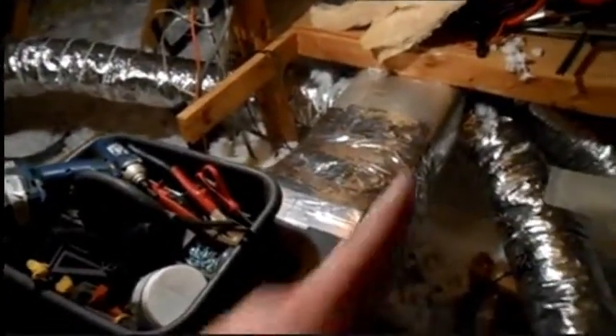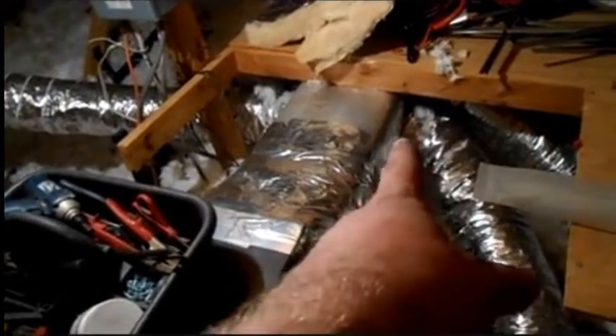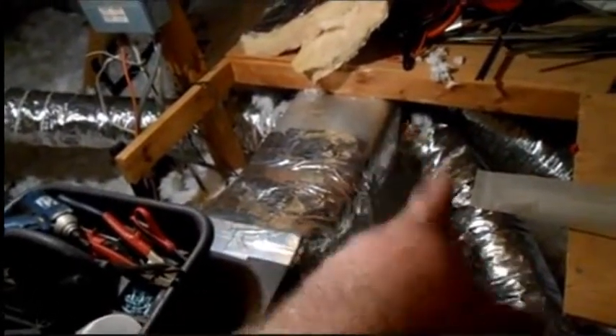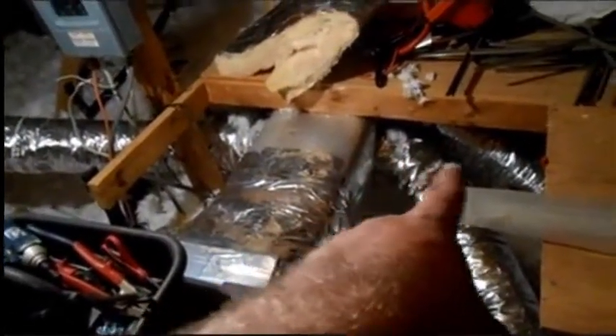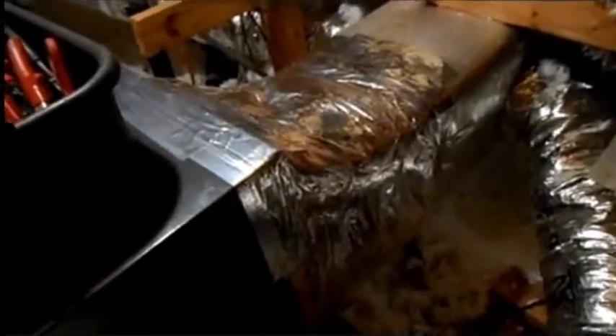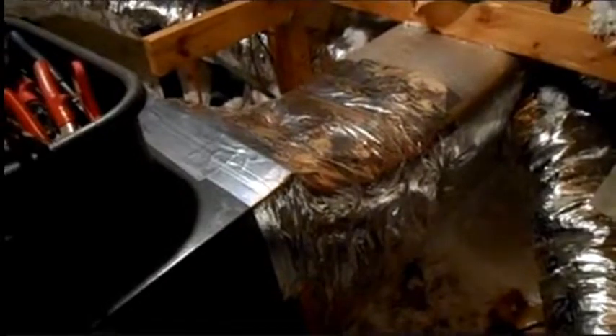There's our supply duct—we hang this one up a little bit here. You don't want the flex coming off and yanking right back this way, so we put a nice smooth bend in it. We have a metal fitting we've insulated on the supply side, adapting it to the old duct. So everything's moving along pretty good.